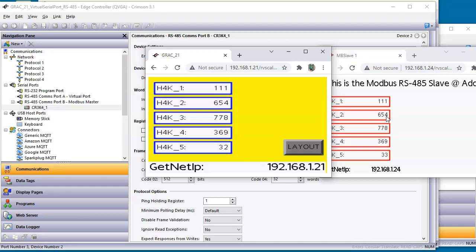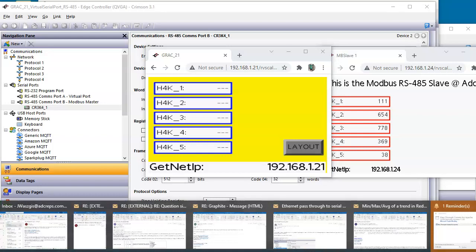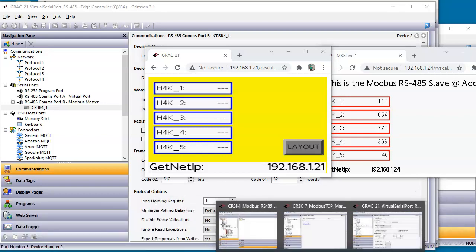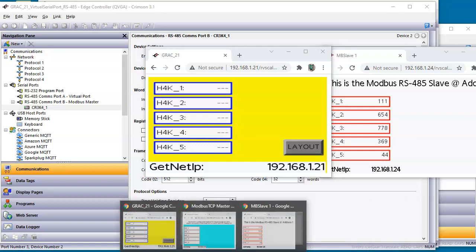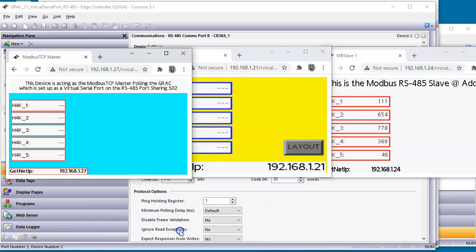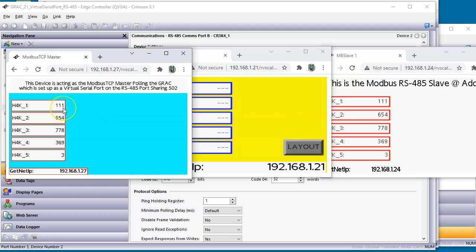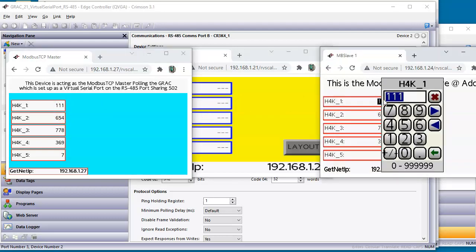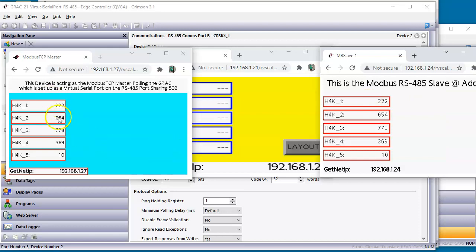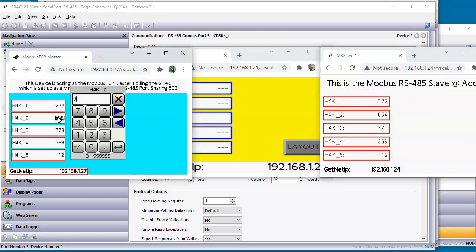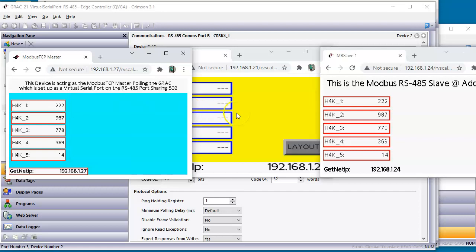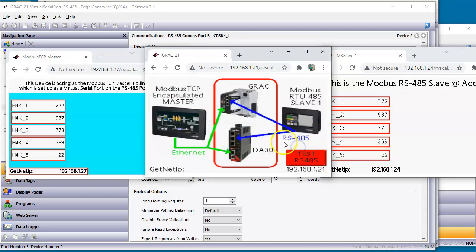Now, if I disconnect that cable from the GRAC, it'll time out right there and you see the dash lines. And if I plug it back in, I get numbers. When you plug these in, I'm getting green and red LEDs blinking very fast on the device. So that establishes communications. Now the next thing I'm going to do is pull up the web page for the master, which is this one right here. This is the guy that's acting as the Modbus master. So if I plug this into the other 485 port on the GRAC, it's doing the virtual serial port. Let me plug it in here. You can see immediately that these are doing the same numbers as over here. So if I change this guy over here to 222, you can see that it changes over here. And if I change this one to 987, it changes over here. Right now, I'm passing through here to this guy on the other port. So that's a really cool demo.